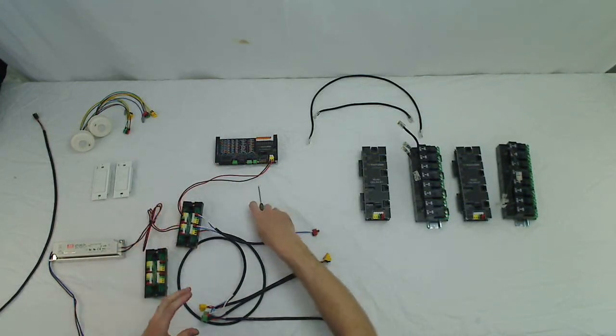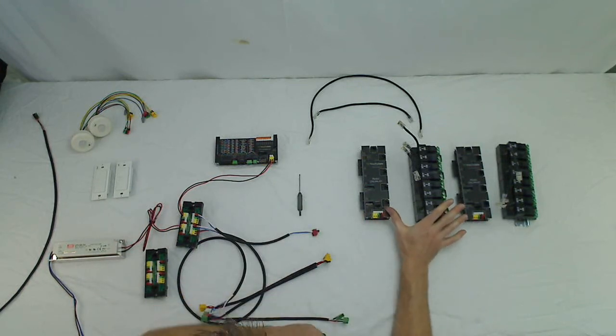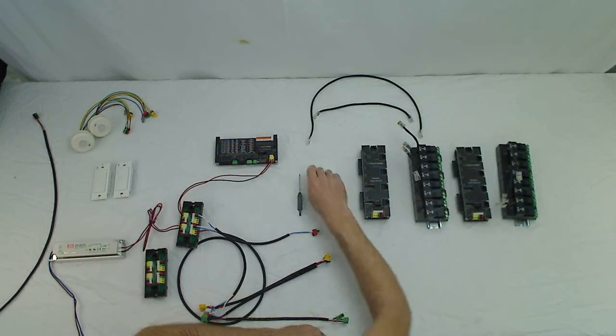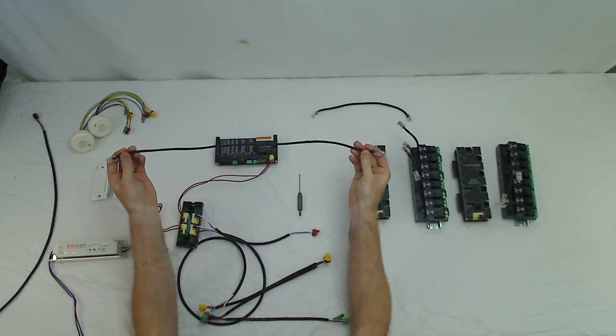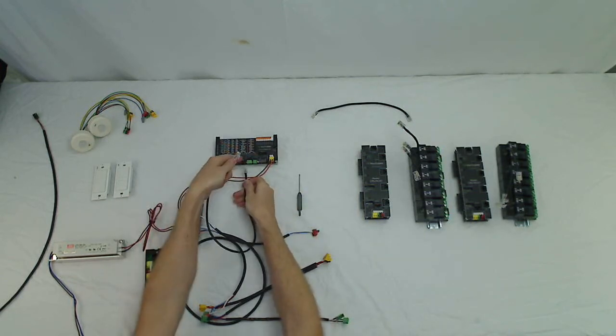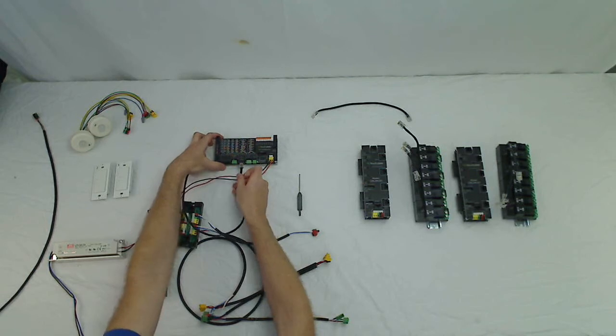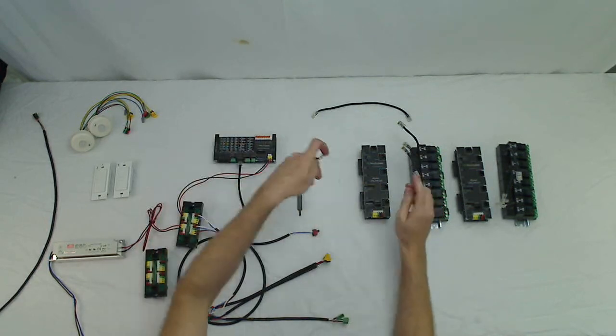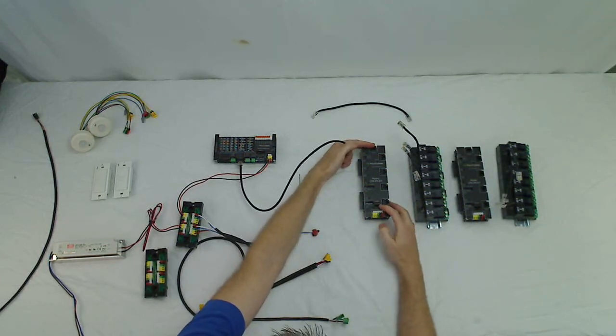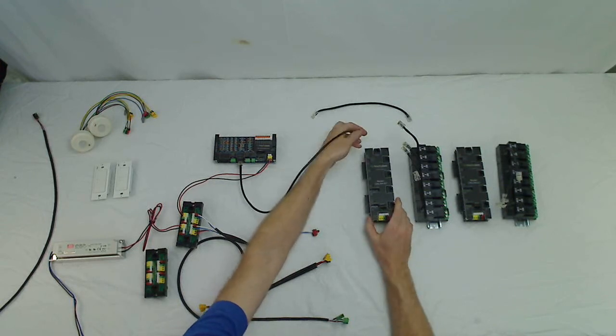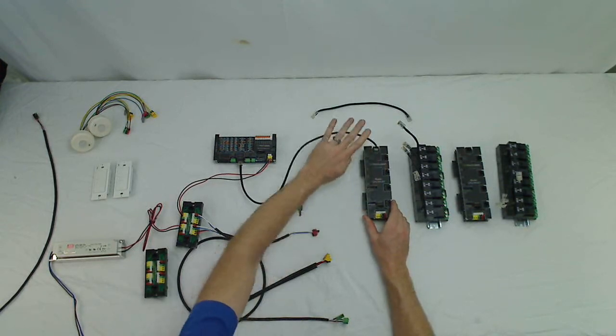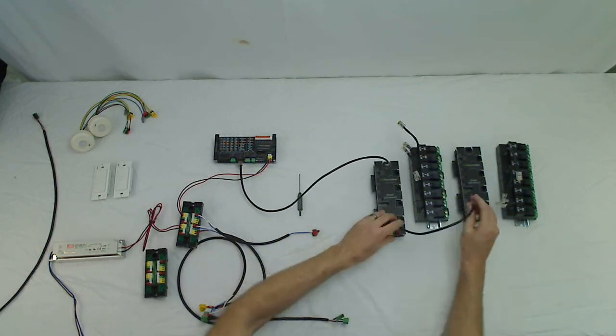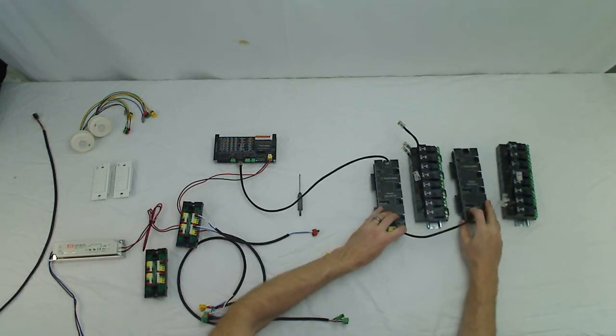Okay, and after we do that, we'll move over to our relay firing cards. The two relay firing cards we're using have already been pre-addressed for address 1 and address 2. So we just use standard Cat5e patch cables. And we'll go from the ethernet jack, labeled to firing cards, and plug in there. And then the upper and lower portion on the firing cards are just passed through RJ45 jacks. So it does not matter whether you start at the top or the bottom. So we'll land to the top and then go from the bottom to the next one. Could be top or bottom, does not matter.